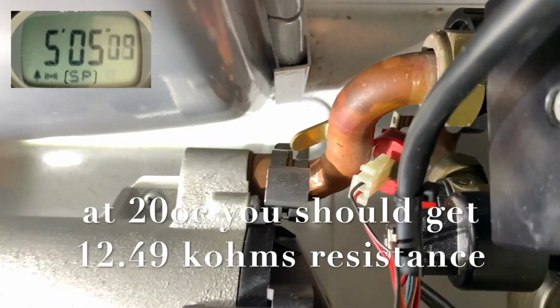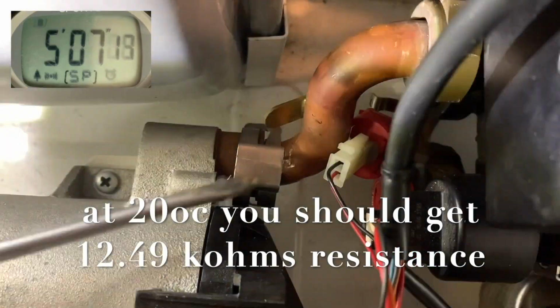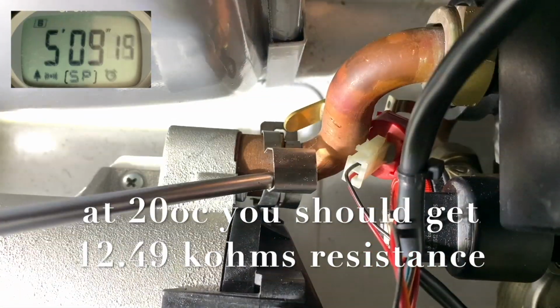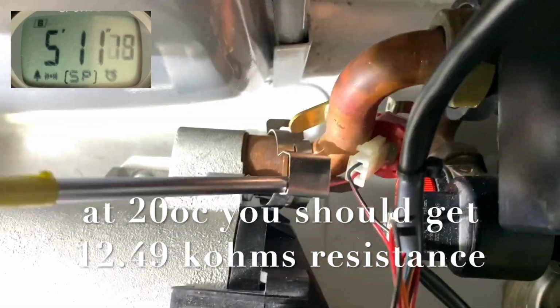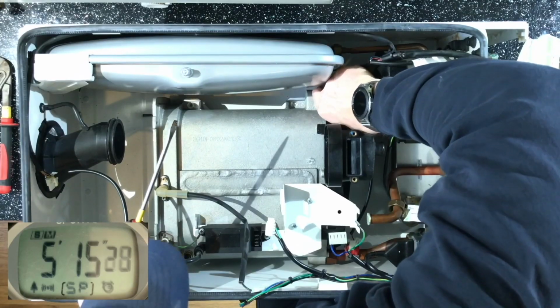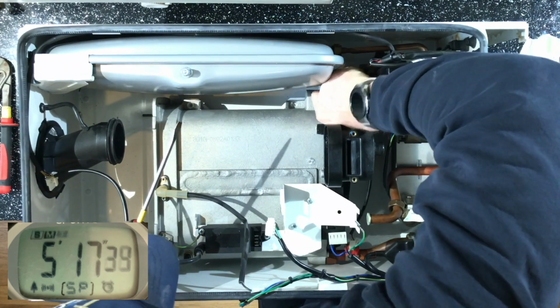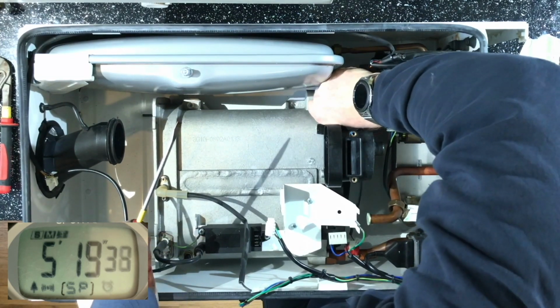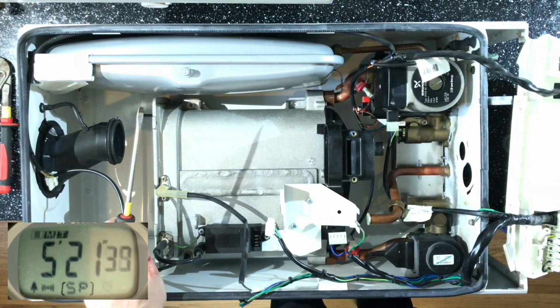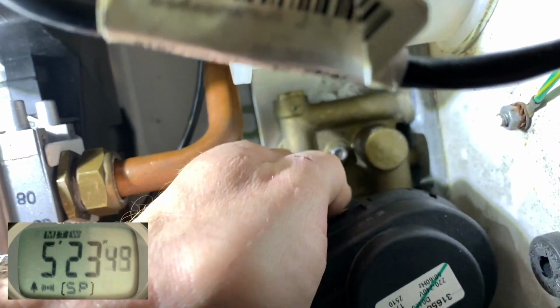Now the next thing I'm going to remove is this, which is the return thermistor. There's also a thermistor on the flow, and there's one at the top of the heat exchanger which I call the hot water thermistor, which is a no flow thermistor, and it turns off the boiler at 105 degrees, so it's like a high limit stat. Now that was the retaining clip which I've just removed on the return pipe. I expected there to be one on the flow, but there actually isn't, so there's only one retaining clip.